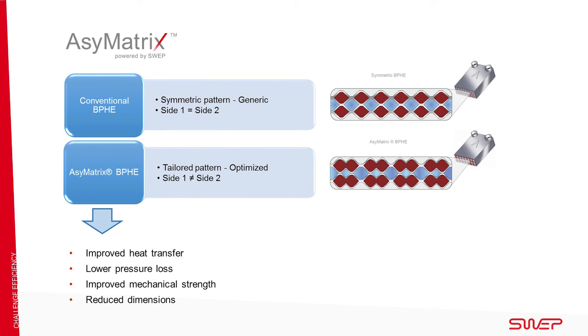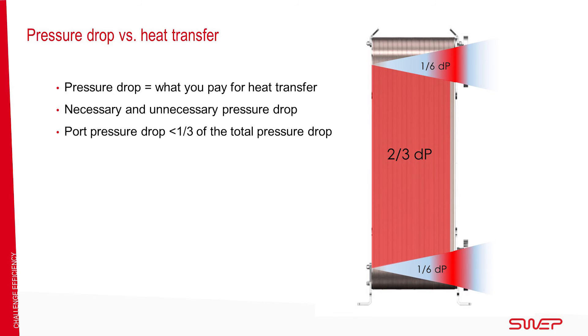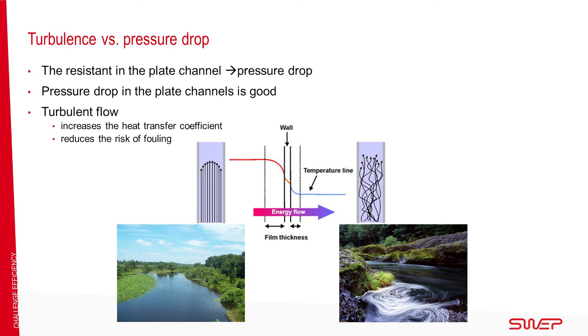Our patented asymmetric design improves heat transfer, which increases the system's thermal performance. It reduces the pressure drop, makes smaller demands on pumps, and increases the unit's mechanical strength. It also reduces dimensions, enabling smaller system solutions. Pressure drop always accompanies heat transfer, but not all of it is always necessary. While pressure drop is essential for heat transfer performance, the connection must not generally account for more than one-third of the total pressure drop. The pressure drop creates turbulence, which is essential for good performance, and it creates the heat transfer coefficient and reduces the risk of fouling.